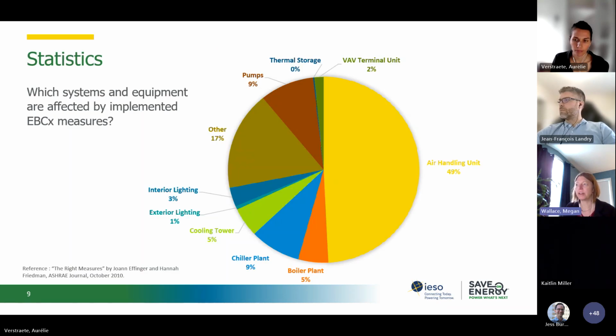So we're just going to go through a few statistics of what we found doing EBCX. The next two slides are based on a US Department of Energy study that looked at more than 100 EBCX jobs for different building types, ages, and sizes. The majority of the buildings were office buildings, but they did look at different building types. And you can see from this pie chart that almost half of the EBCX measures that were implemented were for air handling units. And another 25% were for the heating and cooling plants, so the boiler plant, chiller plant, cooling tower, and the associated pumps.